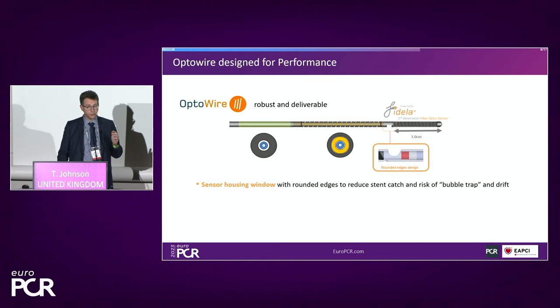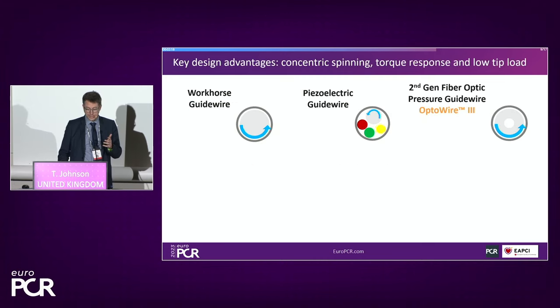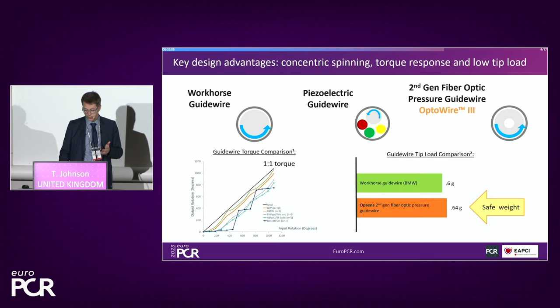The OptoWire is an optical core wire, enabling the construct to behave like a workhorse wire. It has a sensor housing with a rounded tip so it won't catch on stents — there was certainly no issue in this complex bifurcation. It has a very robust shaft with important torque ability. Comparing conceptually to a piezoelectric crystal-type technology, we see far greater one-to-one torque responsiveness, and in terms of weighting, it has a similar weight to a standard BMW workhorse.